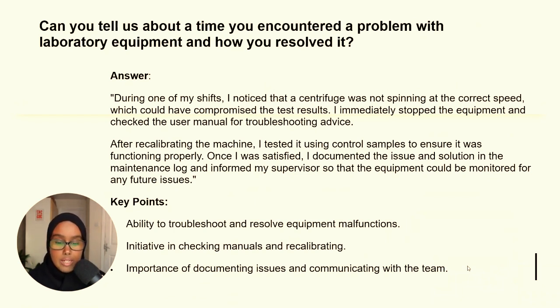So after recalibrating the machine, I tested it using control samples to ensure it was functioning properly. Once I was satisfied, I documented the issue and solution in the maintenance log and informed my supervisor so that the equipment could be monitored for any future issues. So the key points here are the ability to troubleshoot and resolve equipment malfunctions, initiative in checking manuals and recalibrating, and the importance of documenting issues and communicating with the team.